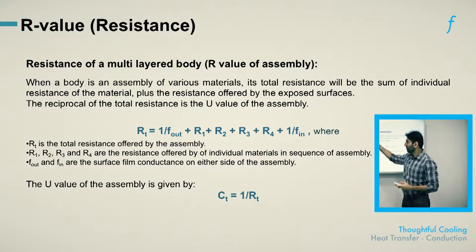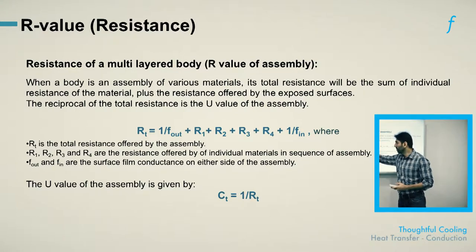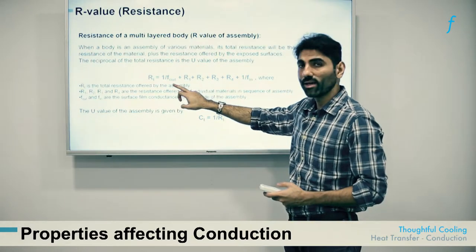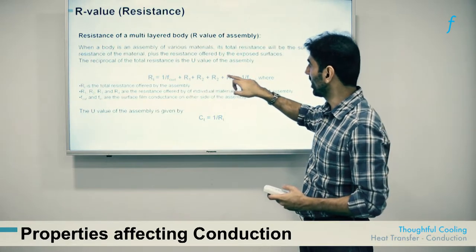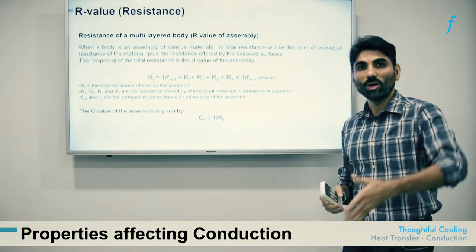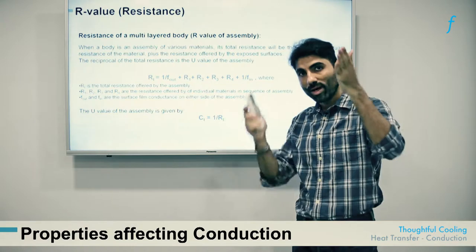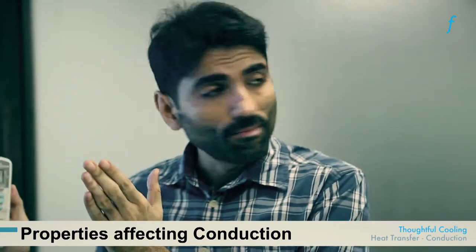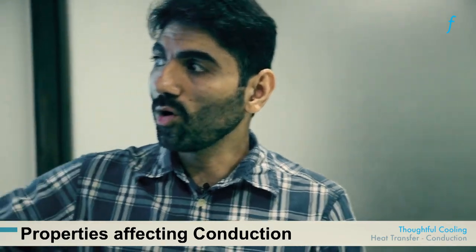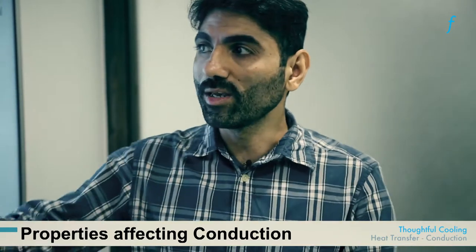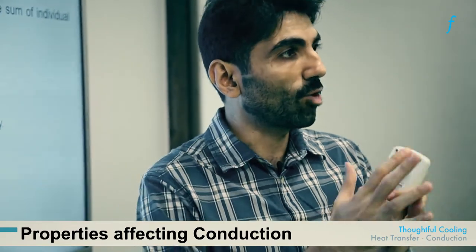This reiterates the mathematical relationship allowing you to calculate the total resistance of a wall: it equals the outside air layer plus the resistance of each individual element in an assembly. For example, a wall could have paint on the outside, plaster, then brick or concrete block as the bulk material, and on the other side cladding, gypsum, and another layer of paint. The resistance of all those layers, plus the inner air layer, must be summed to calculate the total resistance of a complex wall assembly.